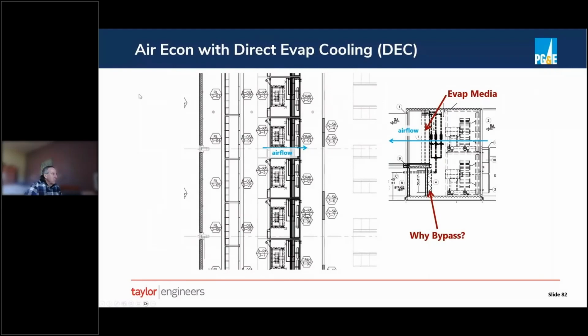Here's a data center that's using direct evap only. This one I think was in Nevada. It's a built-up system. We've got these air handlers, set up like a fan wall. This is a plan view. We've got outside air coming through filters. The return air isn't shown here. There are dampers above coming down from the ceiling plenum. So we've got outside air and return air going through these plenum fans. And then here's a section through the fans, pushing through evaporative media. And then there's a bypass.